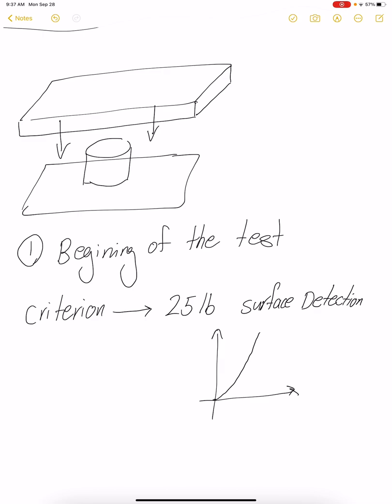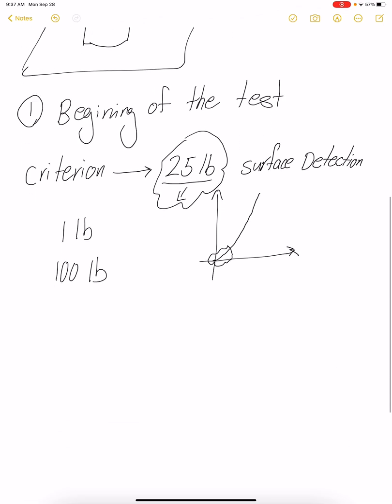But if you have a polymer you might want to use a lower criterion. This force criterion tells us whenever the machine senses 25 pounds that means the surface has been detected and the software starts to record data. If you assign a very low value, let's say one pound, then the machine might detect air friction as the specimen surface and it starts recording data, which would be incorrect. And if you assign 100 pounds, the machine has already applied pressure into the specimen, so we are losing the beginning of our stress-strain curve.